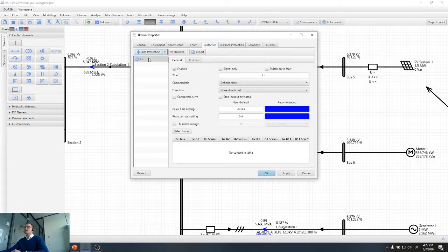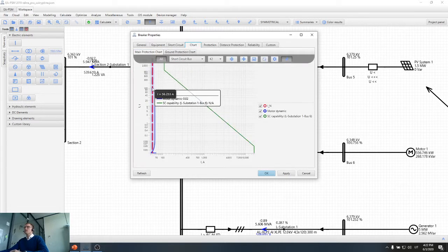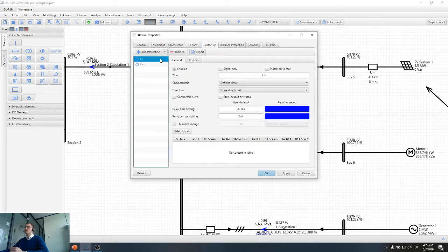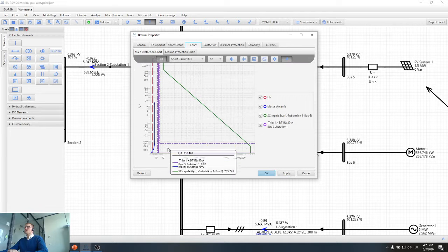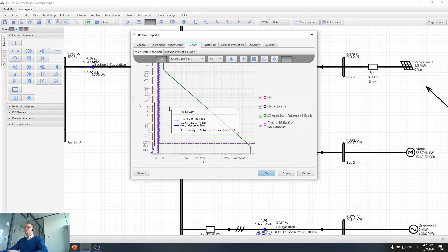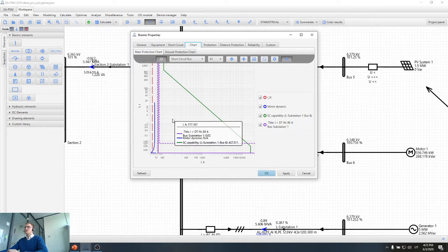numerical relay. So first of all I need to select overcurrent first stage of the numerical relay. So I will select the functionality overcurrent, and also the second stage can be already added. So I will select numerical relay according to the normal operation current. It is 56 amps. So I need to provide some safety margin. I will provide, let's say, like 80 amps current. Operation time 20 milliseconds, and definite time curve. So if I provide these readings, my protection device current and time curve, TCC curve will look like this.